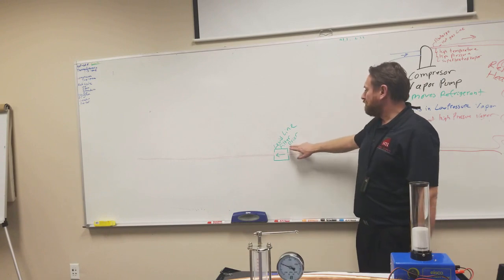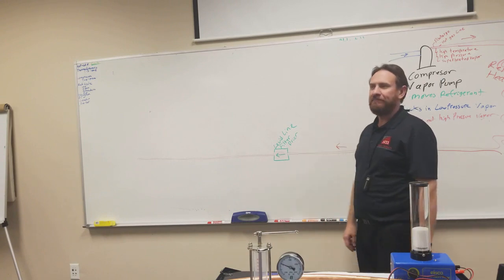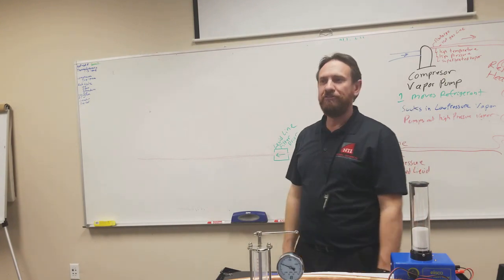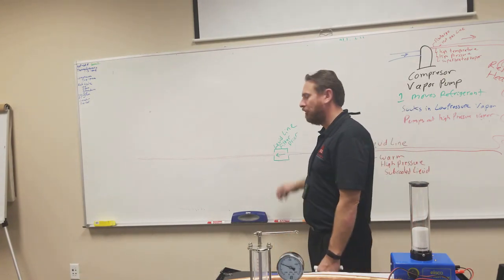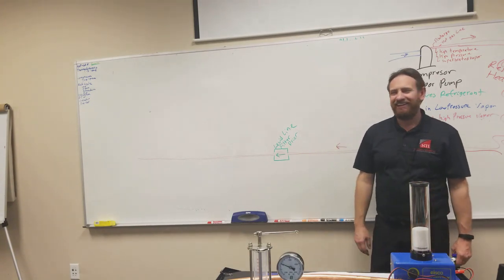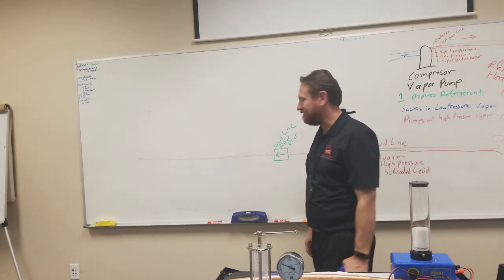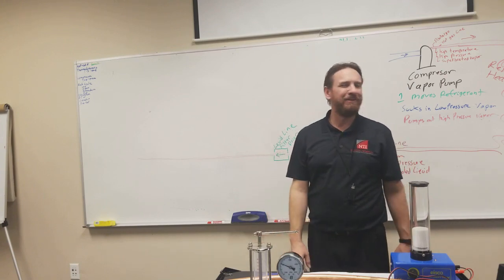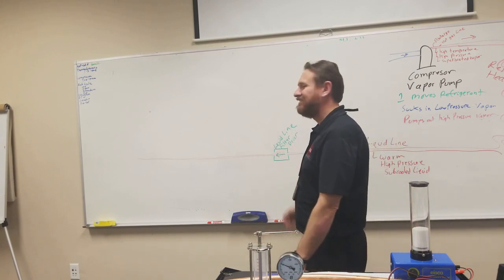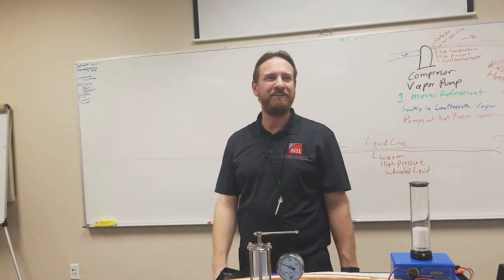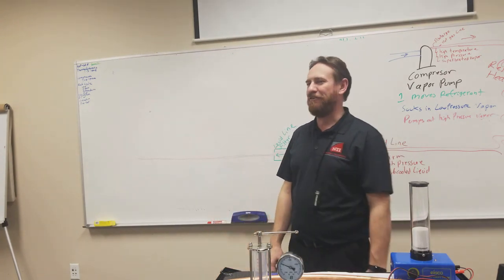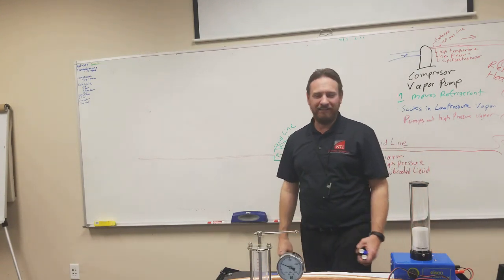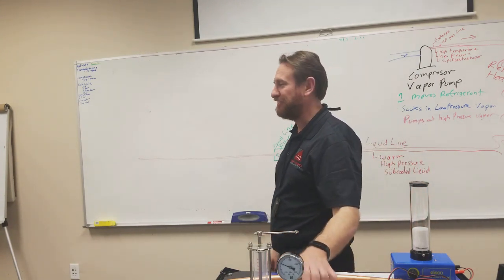So this dryer we change anytime we open the system up. If we don't open the system, there's a way to check it to make sure it's still good, but usually we don't need to change it every year. There was this one lady, she called me and said it's time for me to change my refrigerant and my dryer. I said, what are you talking about? The last company said I had to come and change that out every year because it expires. No. Refrigerant should never wear out. That dryer should never wear out either, unless there's a problem and you have to find what's causing it.